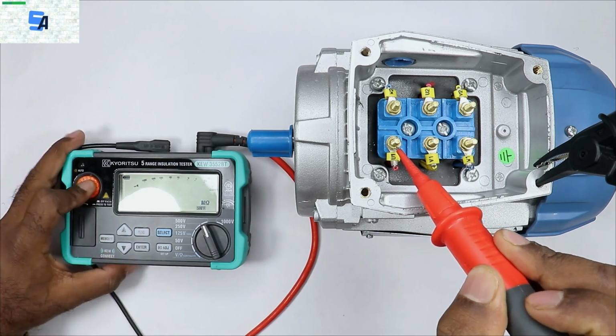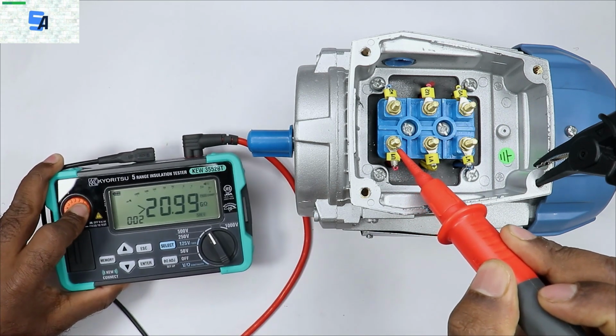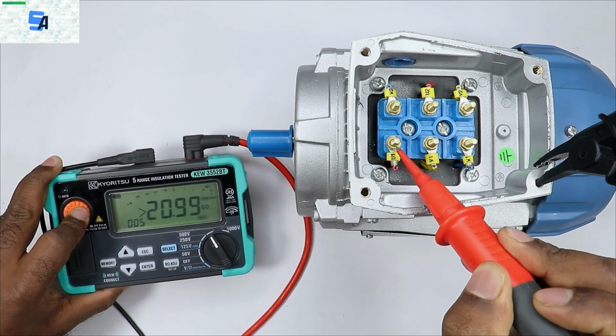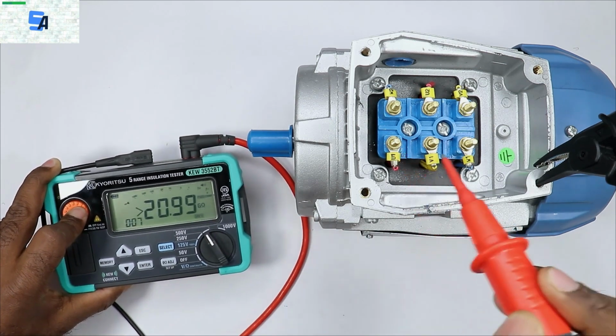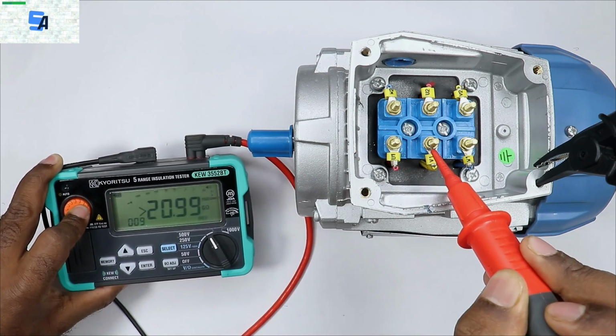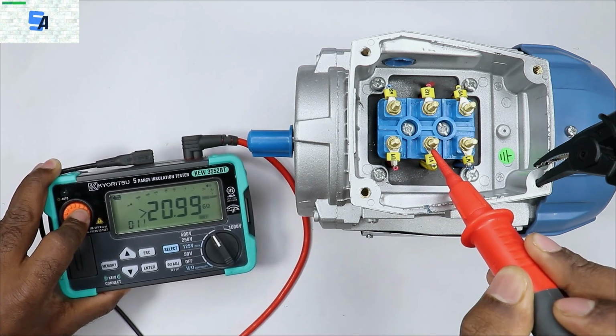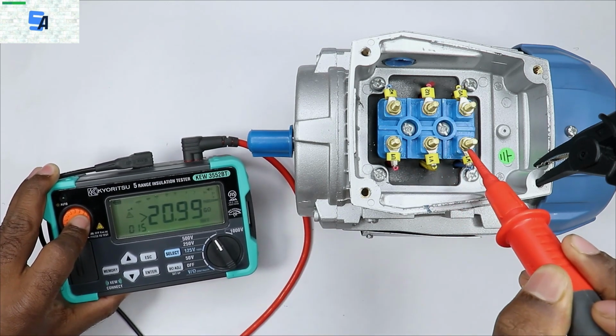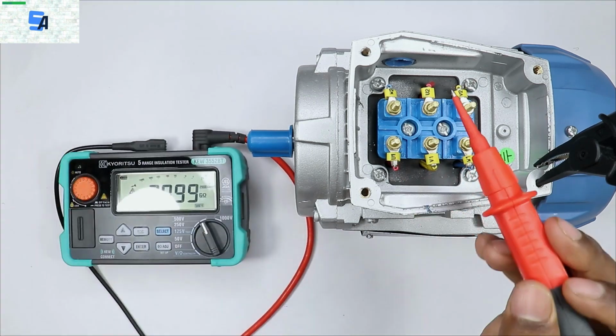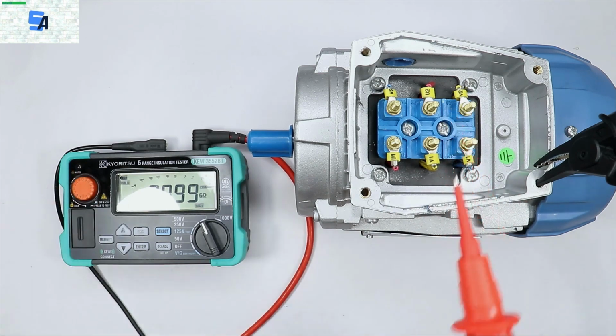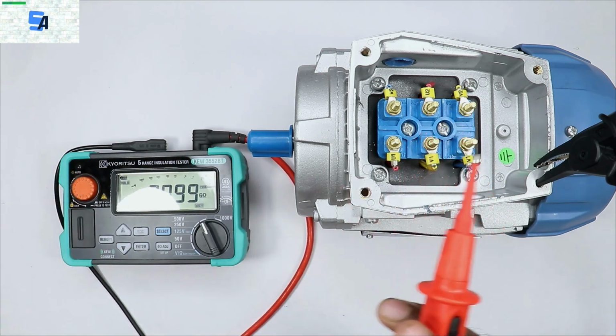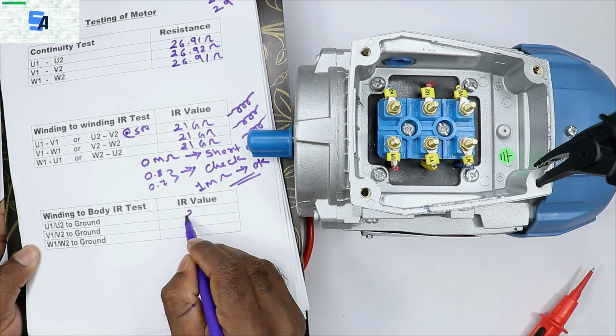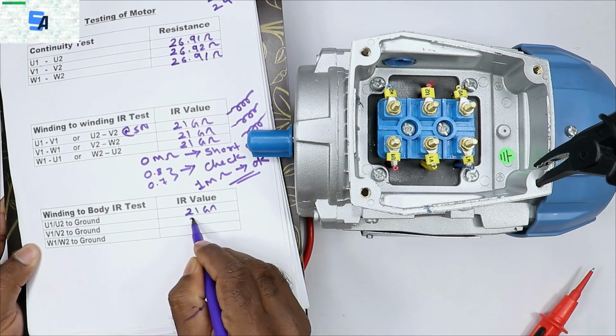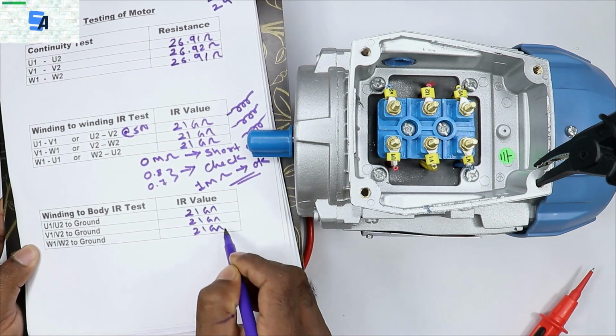After pressing the button, it is showing 20.99 giga ohm. Let's check the other windings also. The IR value of the second winding is 20.99 giga ohm, and the IR value of the third winding is also the same. So the value we got is absolutely perfect. That is, between the winding of the motor and the body of the motor, the insulation resistance is very high. So I am writing here that for all 3 windings we got 21 giga ohm IR value.